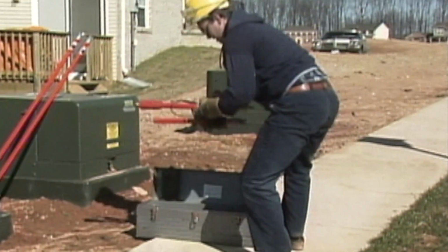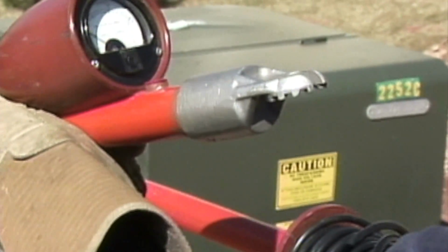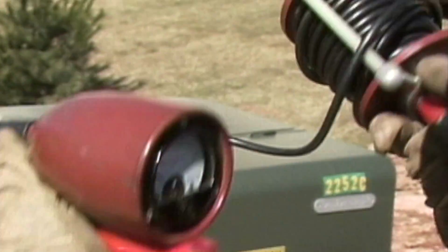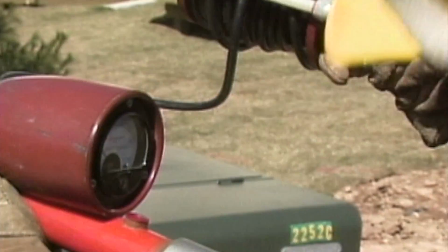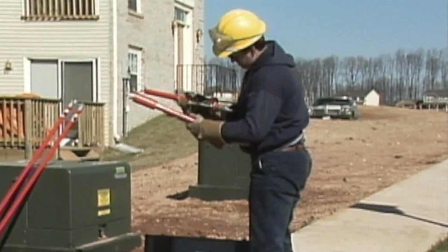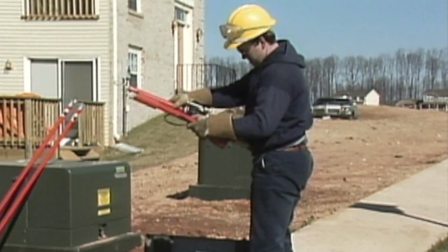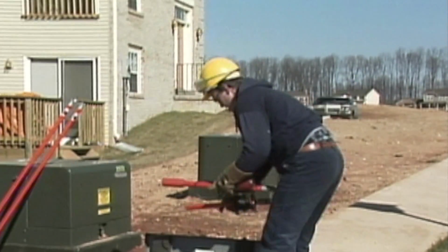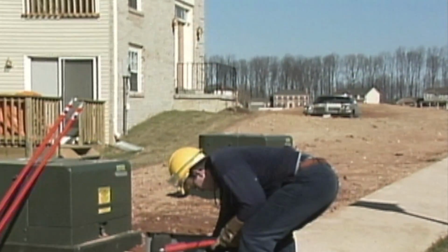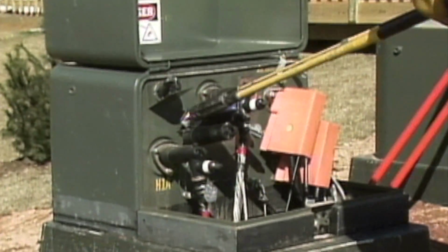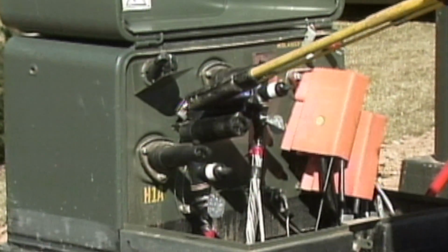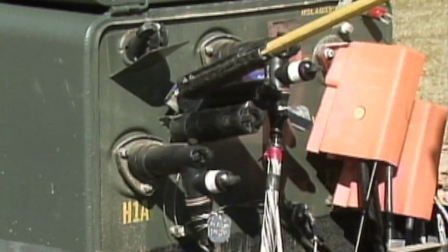Before you use the phasing tool, check the meter carefully for physical defects and look for cracked or worn insulation on the leads. Now let's see how this man uses a phasing tool to test one of the conductors on this transformer for dead. Because this transformer has fully insulated connections, a direct reading with the phasing tool can't be made.